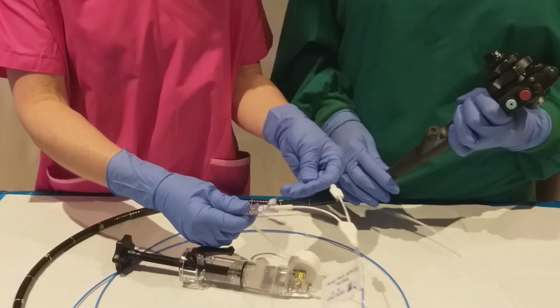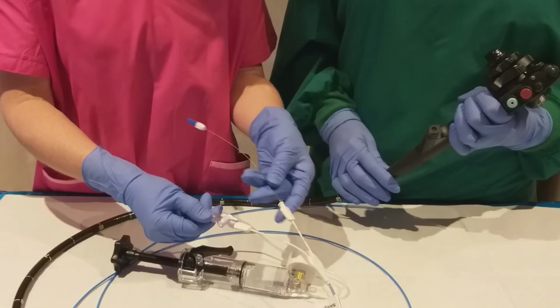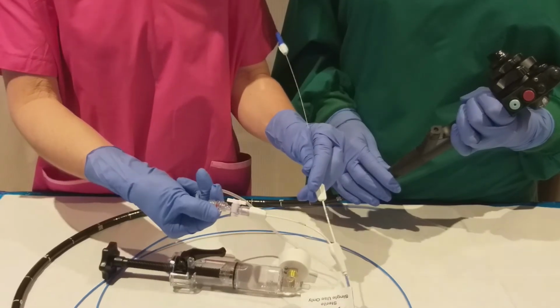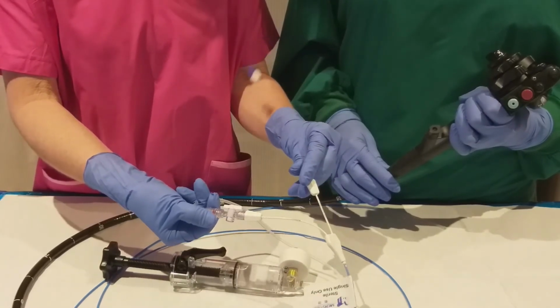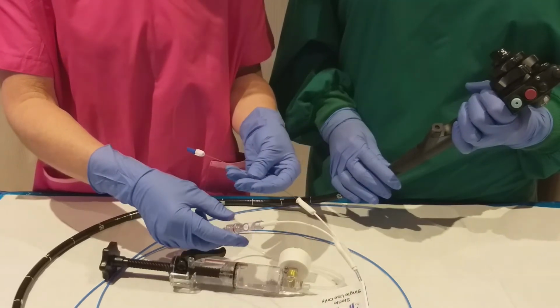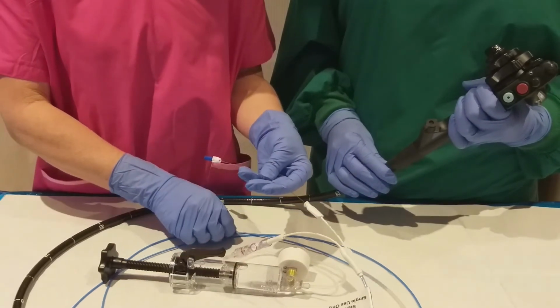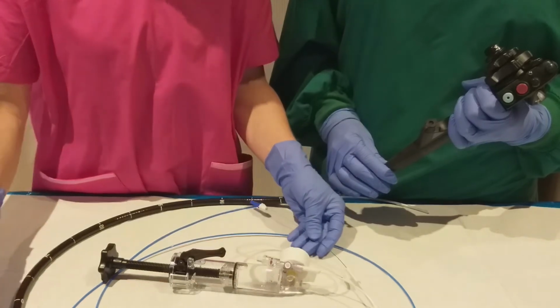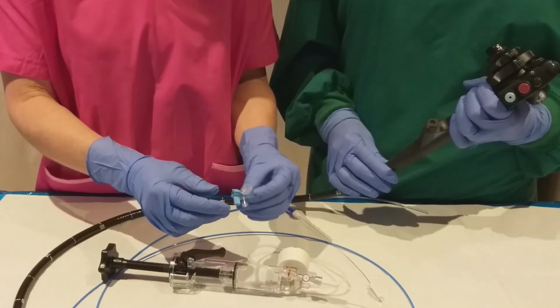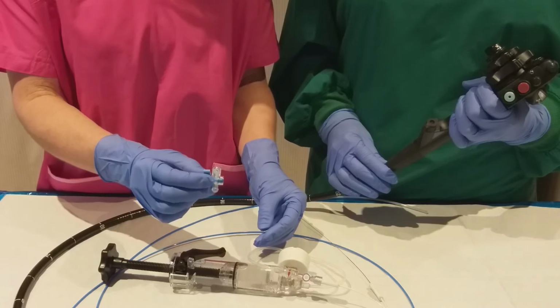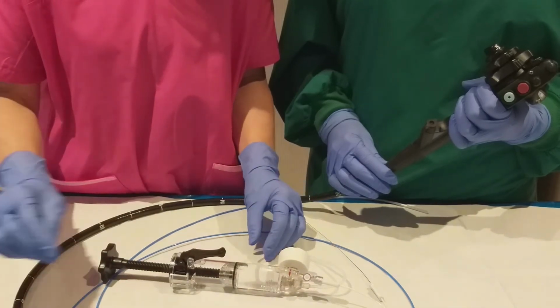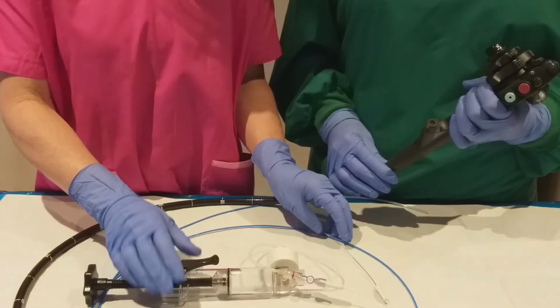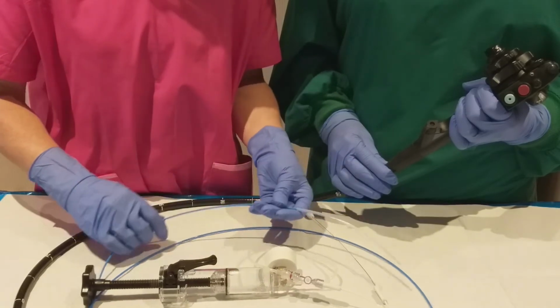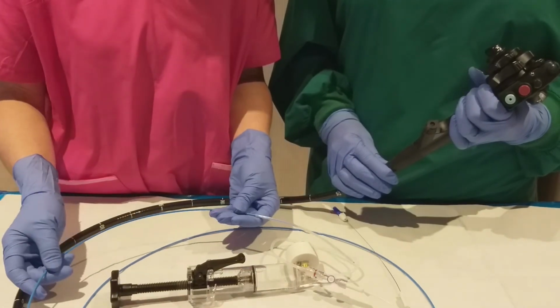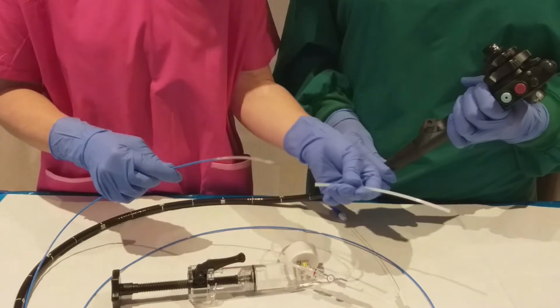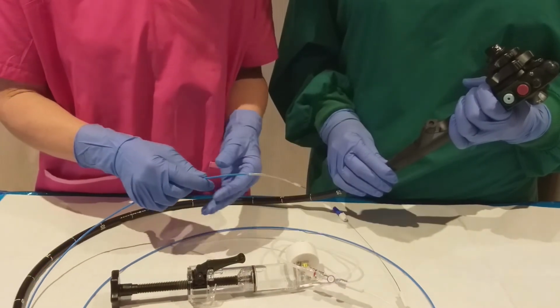The balloon has 2 ports that can be identified as guide wire and balloon. The guide wire assists with catheter insertion and provides the option of guide wire assisted dilatation. A 3-way tap has been provided. It is up to the individual if they choose to use this, but it is not necessary for the procedure. The 3-way tap is useful when you need to add sterile water to the inflation syringe and/or to expel water or air. Remove the plastic sheath from the distal end of the balloon. The device is now ready to be inserted down the biopsy channel.